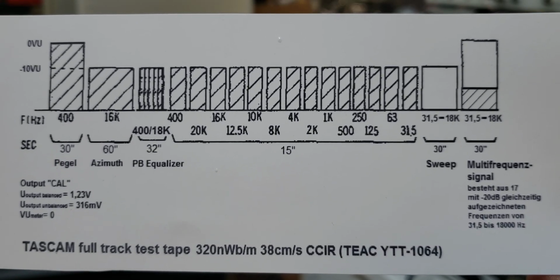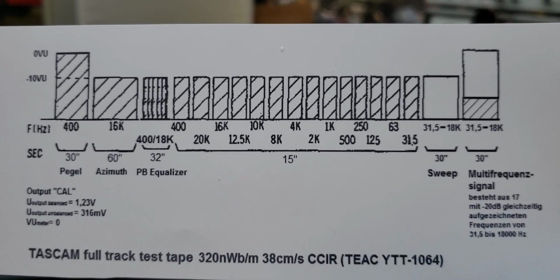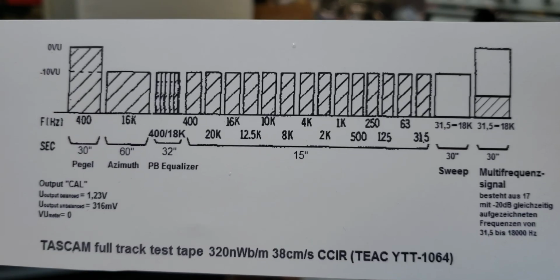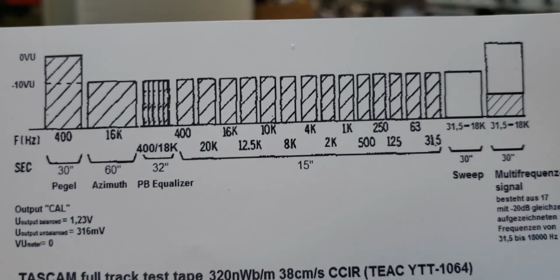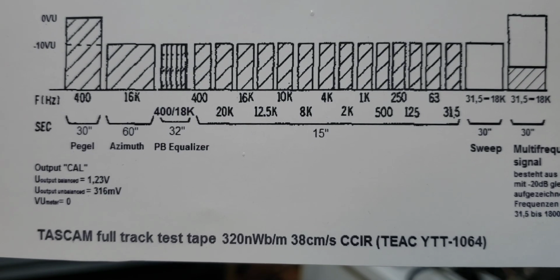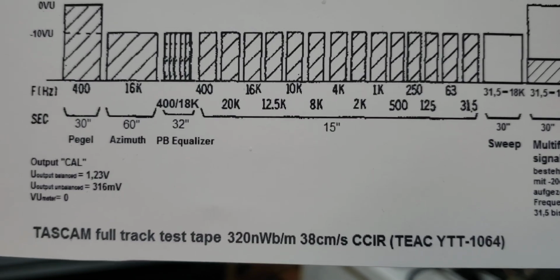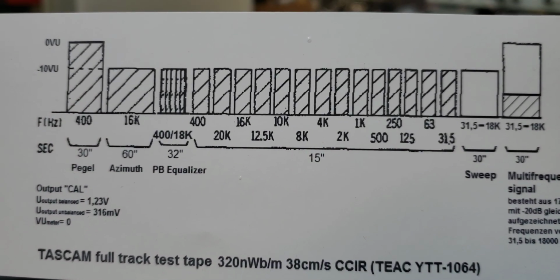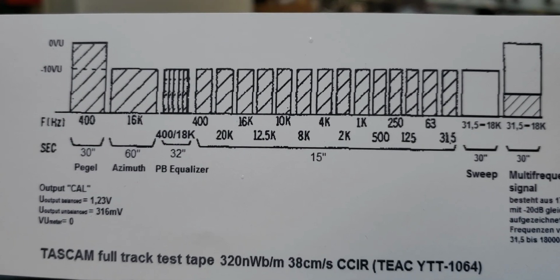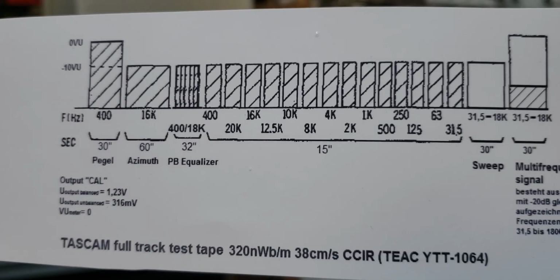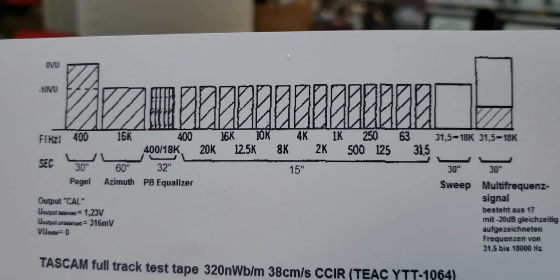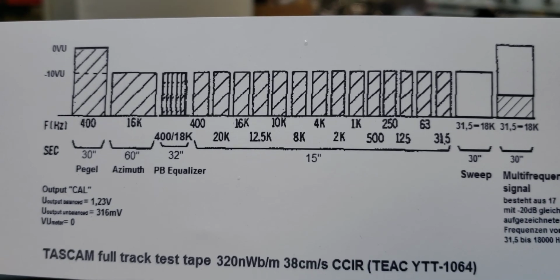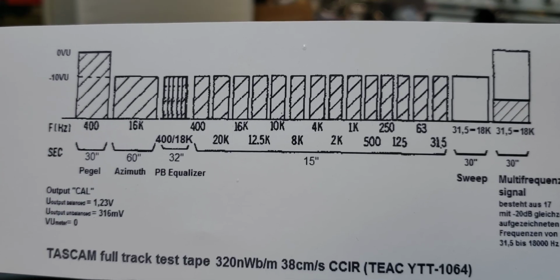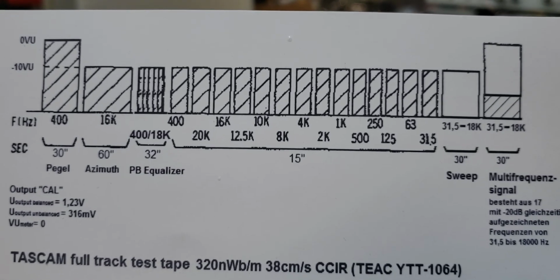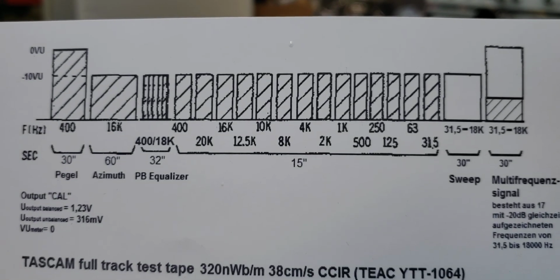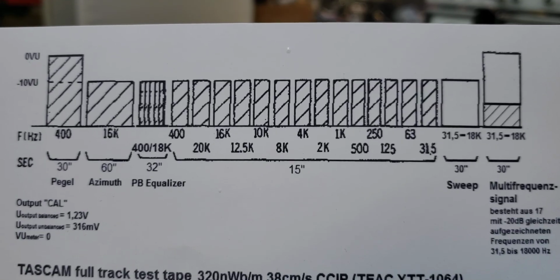It starts with a 400 Hz tone at minus 10 dB. And this is where your equalization is going to be happening. So you use this tone as a reference level for all other measurements when you're doing frequency response calibration. It is followed by the sequence of 20, 16, 12.5, 10 kilohertz, and all the way down to low frequencies, 500, 250, 125, 63, and 31.5 hertz. That allows you to test pretty much the whole range of the machine's operation. And then there are some additional tones, but we're going to disregard them for now. So if you're looking for a good test tape, I certainly recommend this one.